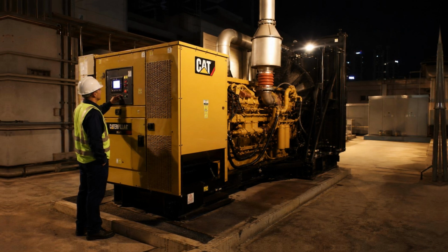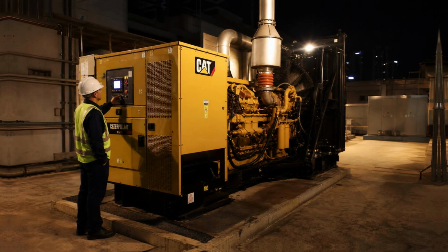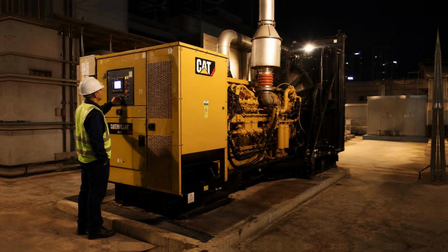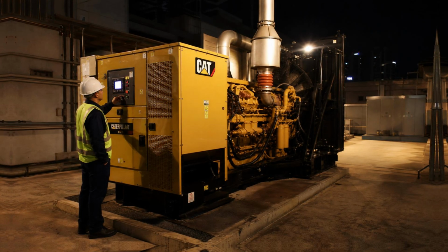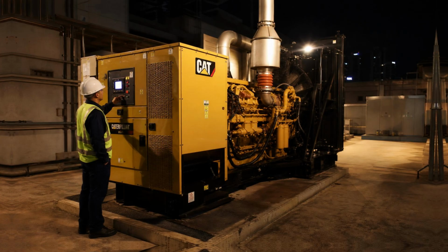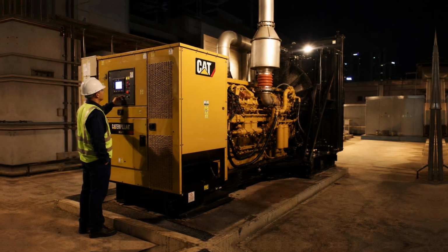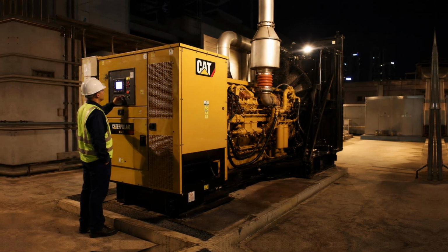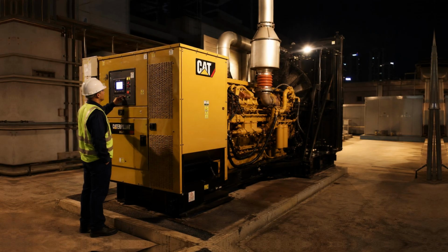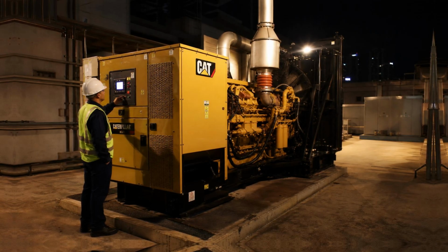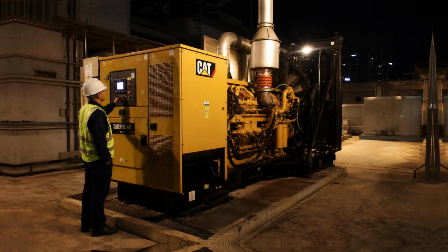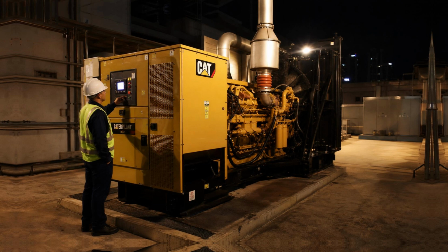Low fuel alarms that trigger when the level drops below a defined threshold, signaling that a fuel delivery needs to be arranged before the reserve runs out. Transfer pumps that move fuel from the main storage tank to the day tank when the day tank's level drops, automatically and without manual intervention, keeping the local supply maintained throughout a long outage.